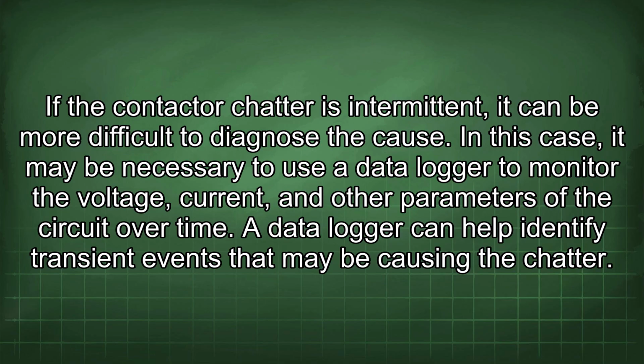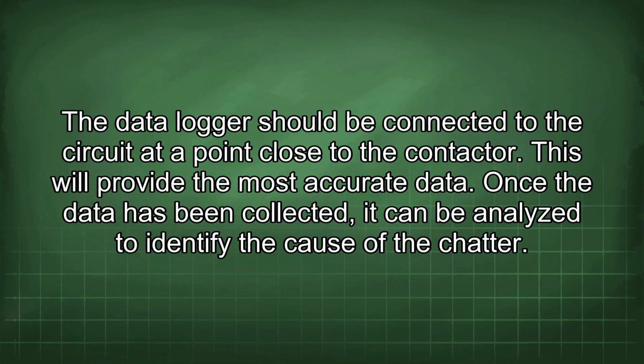If the contactor chatter is intermittent, it can be more difficult to diagnose the cause. In this case, it may be necessary to use a data logger to monitor the voltage, current, and other parameters of the circuit over time. A data logger can help identify transient events that may be causing the chatter. The data logger should be connected to the circuit at a point close to the contactor. This will provide the most accurate data. Once the data has been collected, it can be analyzed to identify the cause of the chatter.